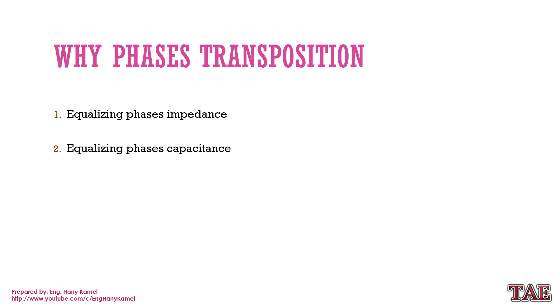First of all, we need to know why we need to make phase transposition. An overhead line with vertical arrangement between phases — the clearance or the distance between phases and phase to ground will not be equal or the same. So the parameter for each phase will be different, like inductance and capacitance. So when we make transposition, the overall inductance and capacitance for each phase will be the same, so the parameters for each phase will be equal.